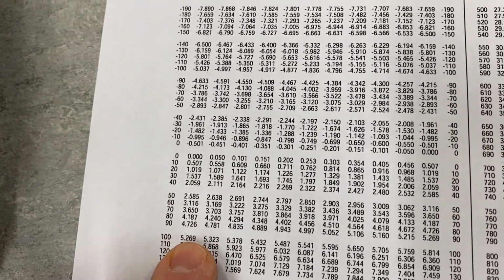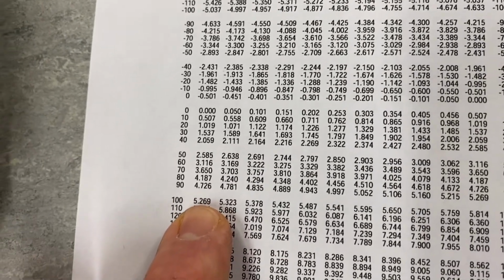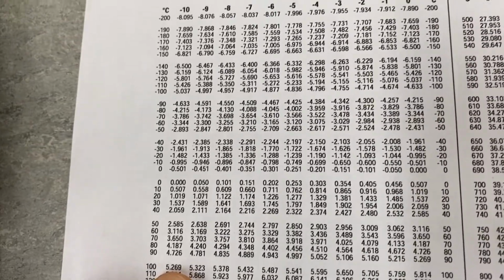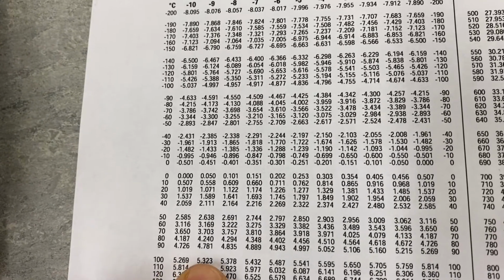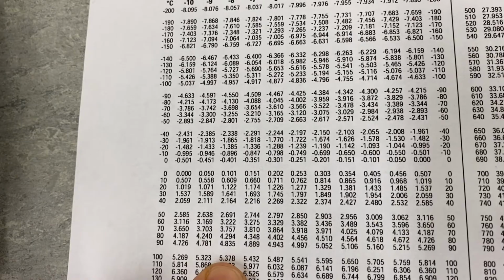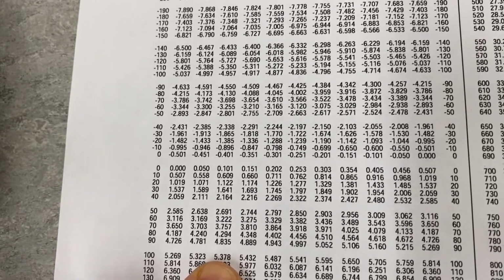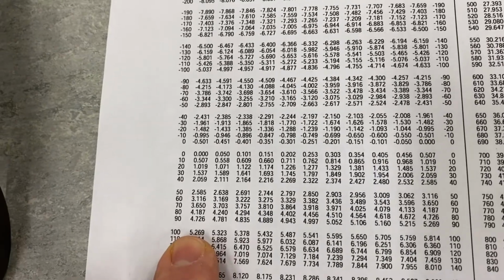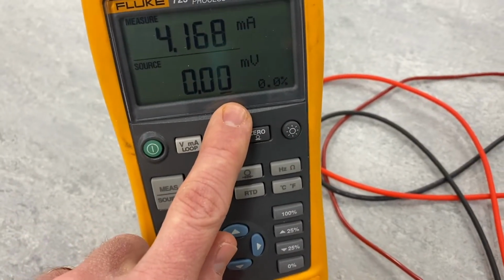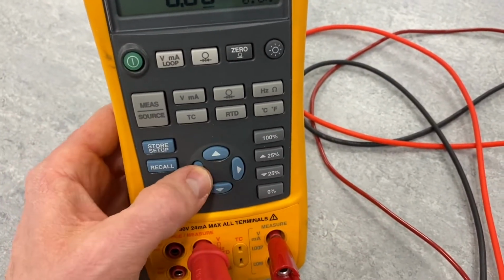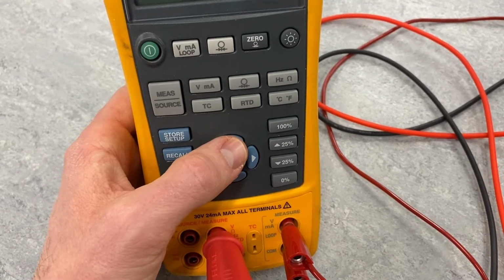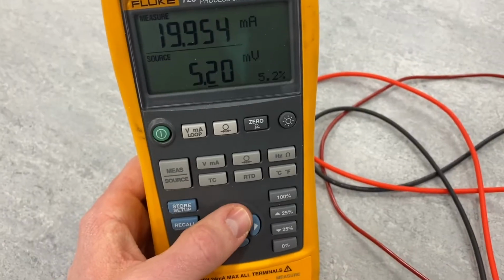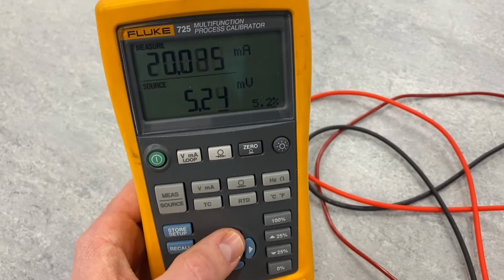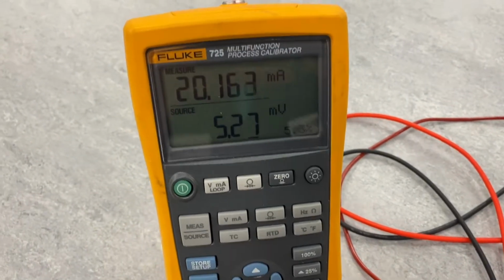Since we want to calibrate this for 0 to 100 degrees, we need to find 100 degrees, which is right here. So the value we need to input is 5.269 millivolts. If we were doing 101, it would be 5.323. If we're doing 102, it would be 5.378, and so on. So these go up in an increment of 1 degree. So this is the value we're going to source. It'll be 5.27 actually, because our millivolt meter only has 2 decimal places here, you can see. So let's input that 5.27. So you've inputted a value of 5.27.